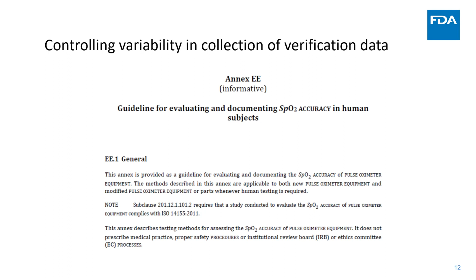It is not an exhaustive means for demonstrating how to calibrate an oximeter. It is simply a qualification test based on a limited number of samples to make sure that the products you're putting on the market perform up to some minimum standards. You, as a purchaser of a particular device, are certainly free to augment and do more. And in fact, in some cases, the FDA guidance document has additional requirements because we thought that they should be more stringent.